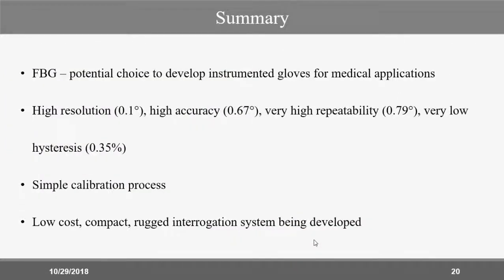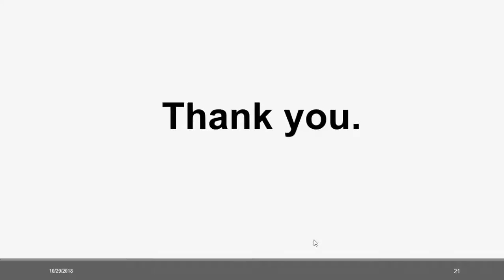In summary, FBG sensors are a potential choice for developing instrumented gloves for medical applications due to the high resolution of 0.1 degrees, high accuracy, high repeatability, and very low hysteresis error we've achieved. The calibration process is simple because the response is linear, and we're also working on developing a low-cost, rugged interrogation system for our glove. That's all for today. Thank you for your attention.